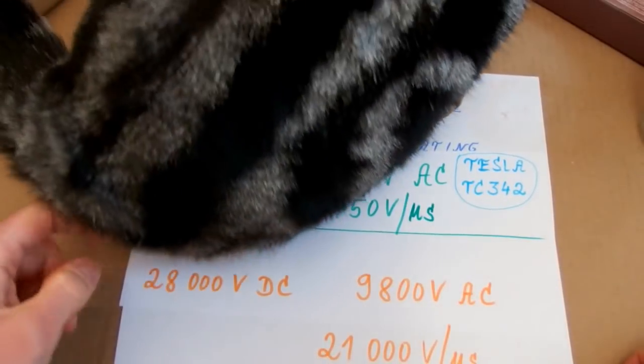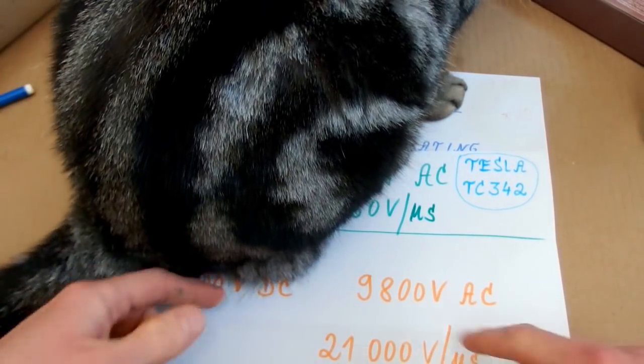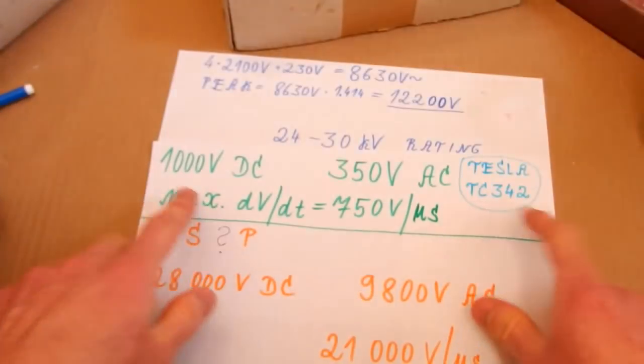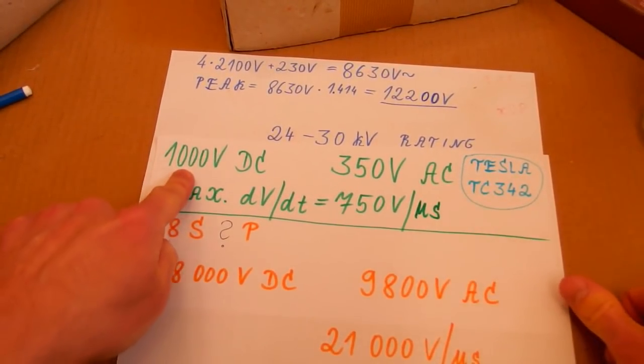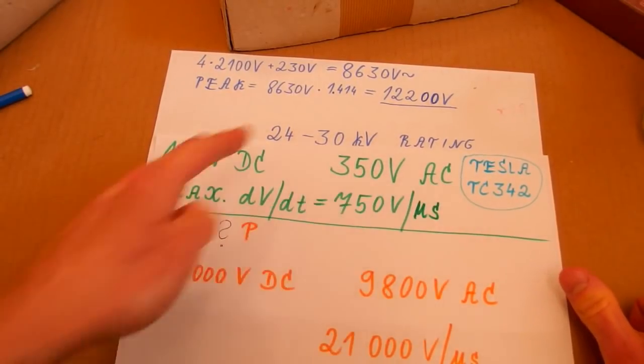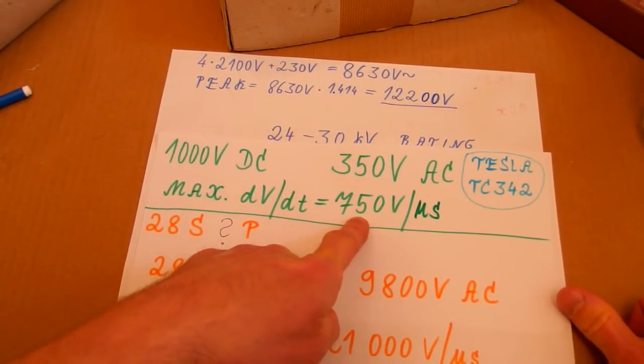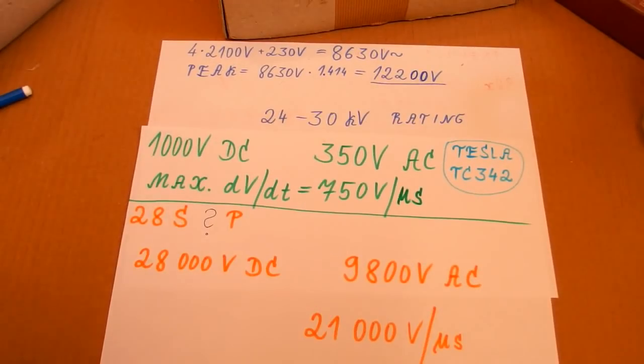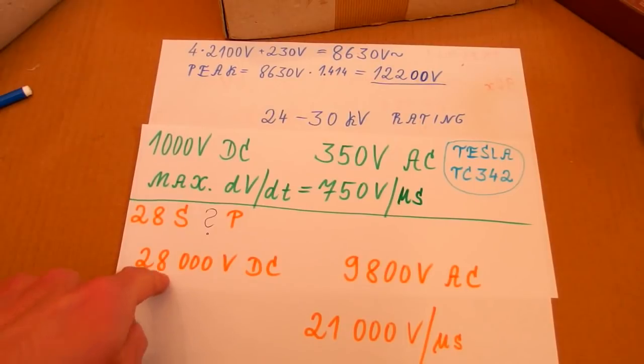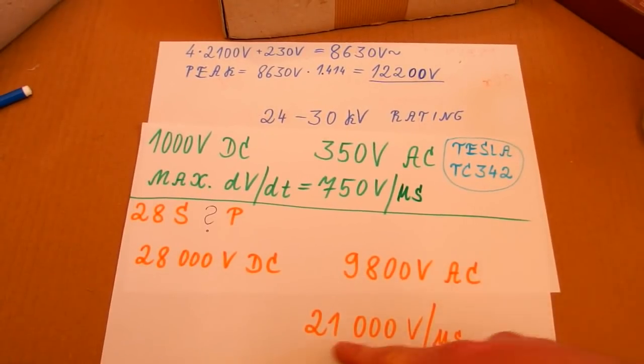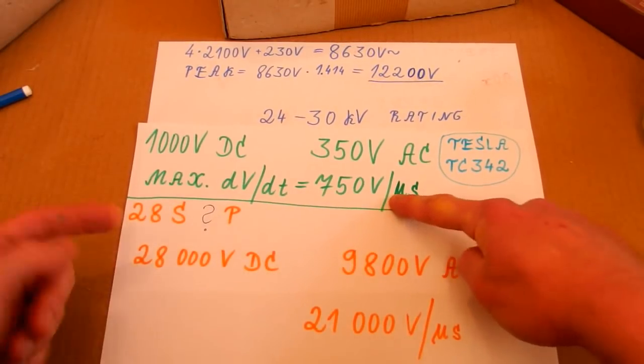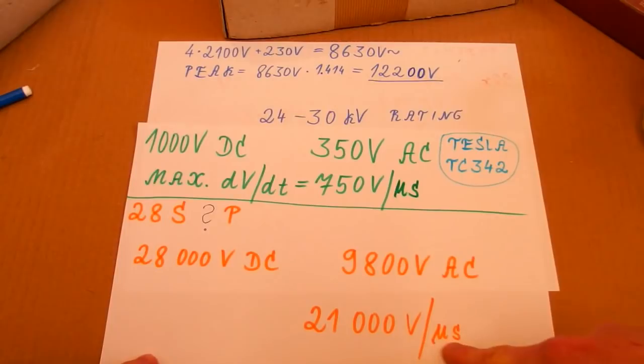So here are my calculations, and let's take a look at it. I decided to put 28 capacitors in series, and of course the voltage adds up, so it gives me 28,000 volts DC rating. And also here you can see some other data of the capacitors: they are 1000 volts DC, 350 volts AC, and their maximum dV/dt is 750 volts per microsecond. So 28 capacitors in series have this voltage rating for DC, this AC voltage rating, and also this dV/dt rating also adds up when you put capacitors in series. So in total this is going to have 21,000 volts per microsecond.